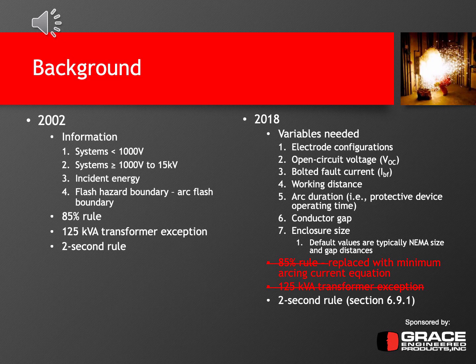So in comparing the 2002 edition and 2018 edition standards with each other as far as what's required and what are some of your inputs and what are some exceptions, the 2002 edition basically was broken down into 2 separate branches. The first branch, or the path they put you on, was if the system voltage was 1,000 volts or less than 1,000 volts, you would go down branch A, which would then take you through certain equations and you'd make some calculations. The second branch was if the system voltage was between 1,000 volts and 15 kV, then you would go down the second branch and then find your results.